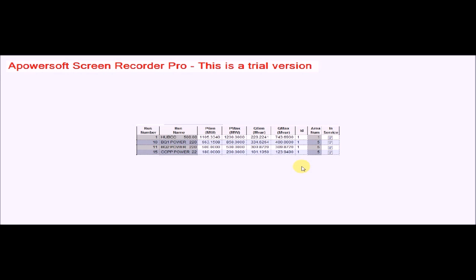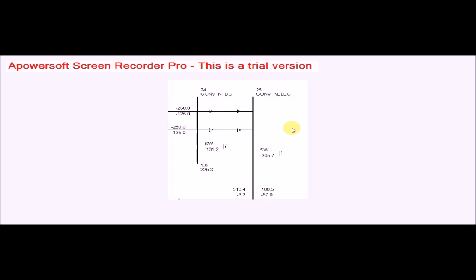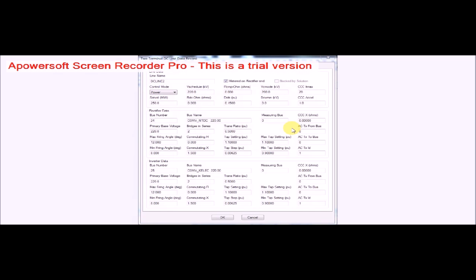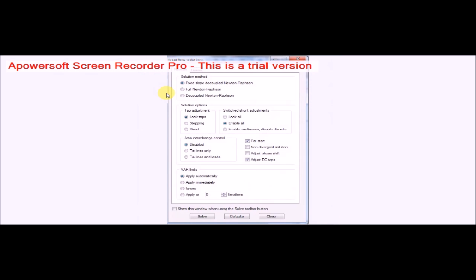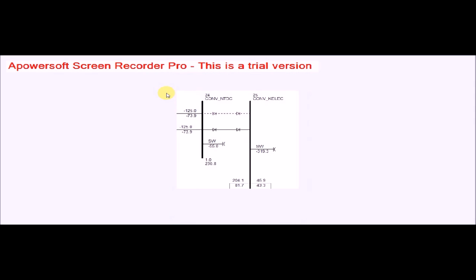The contingency analysis considers different scenarios in which a component of the system is taken out and the power flow is then analyzed. In the first case, we take out one of the DC lines. We can see the initial power generation at the generators. To take out the DC line, we go to the control mode and select 'blocked' rather than 'power mode,' then run the load flow solution again — one of the DC lines has been taken out. We then check whether the system steady-state response varies and whether isolation between the two utilities has been achieved.